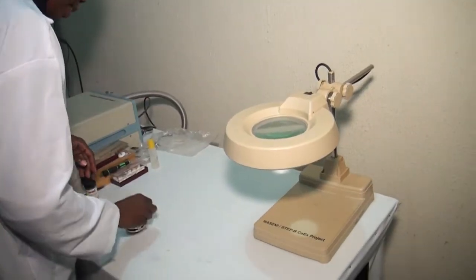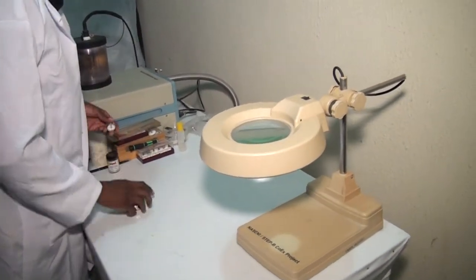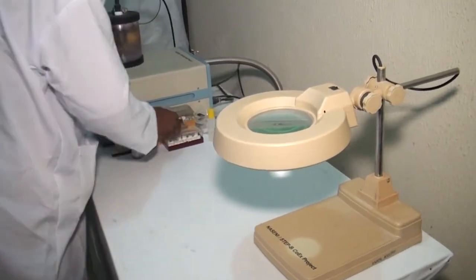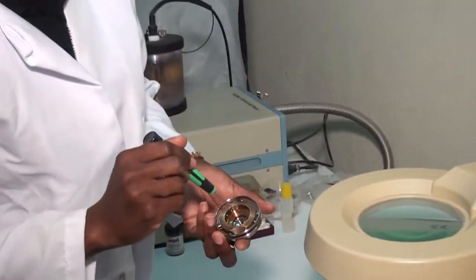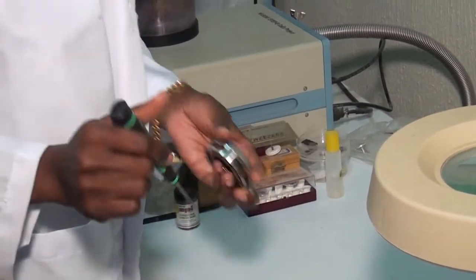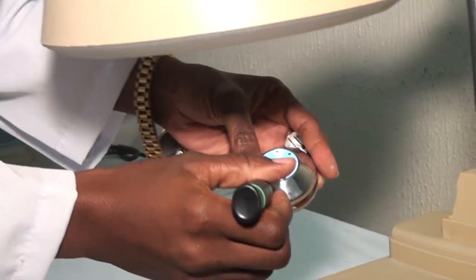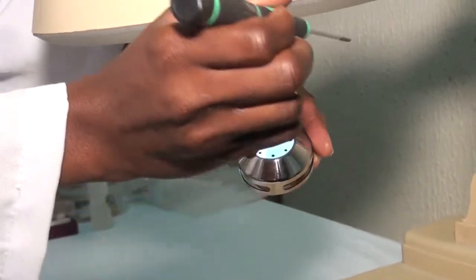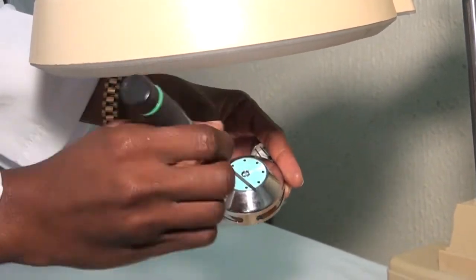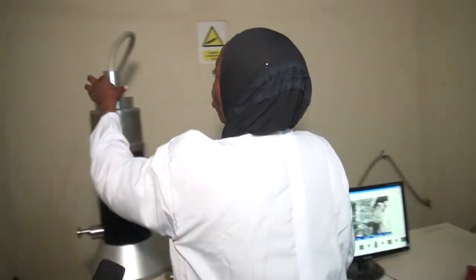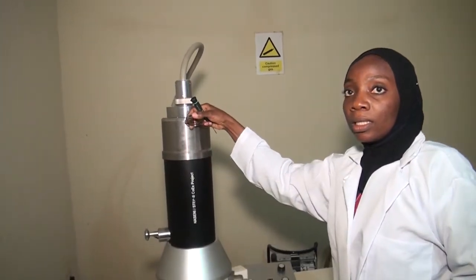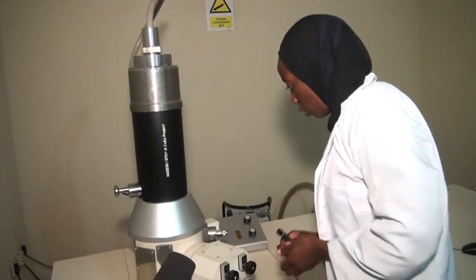After that, we come to this side. This is our magnifying lens, and this is our filament. We open this under the magnifying lens, and we set the filament at the center. It is important to set it at the center because the filament is what generates electrons. From there, we bring it here, open this, insert this. Then after that, we can now start the operation.